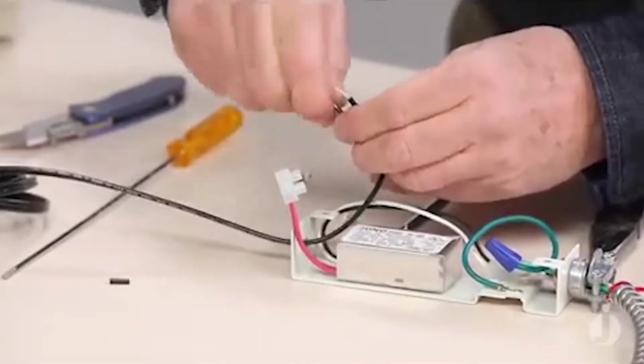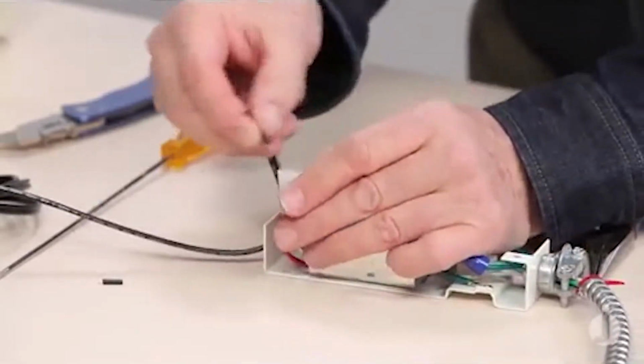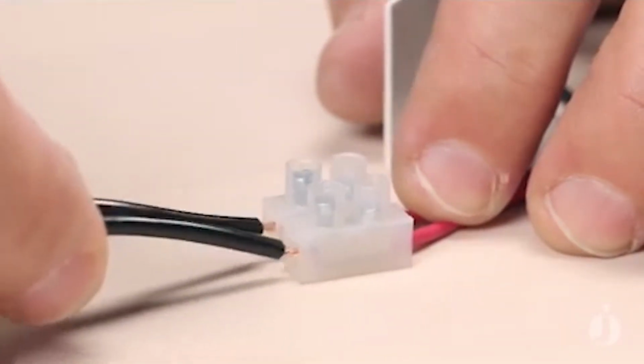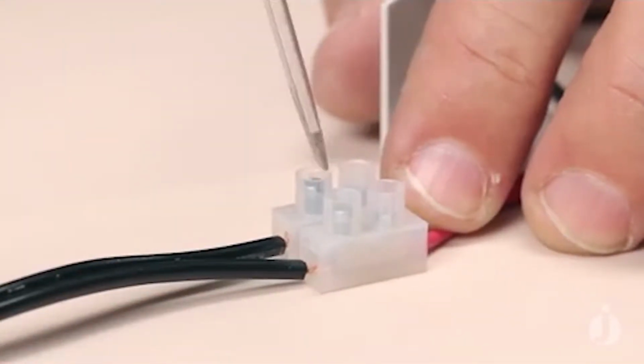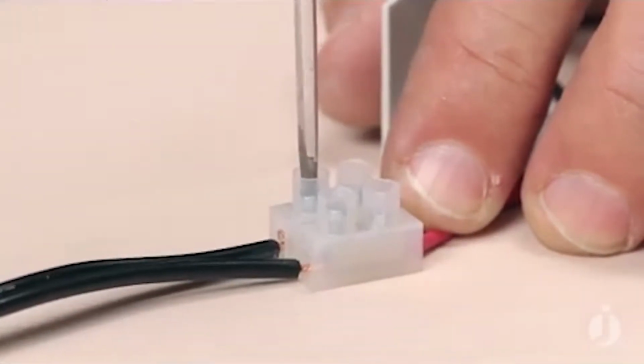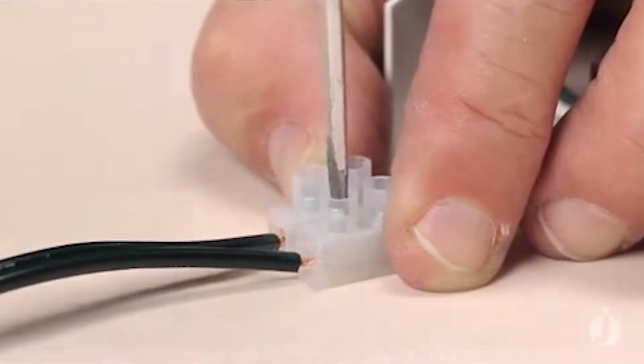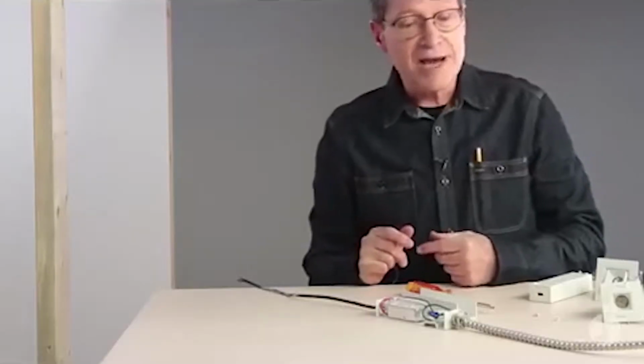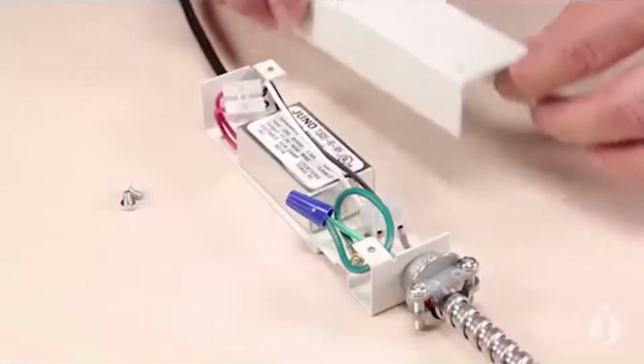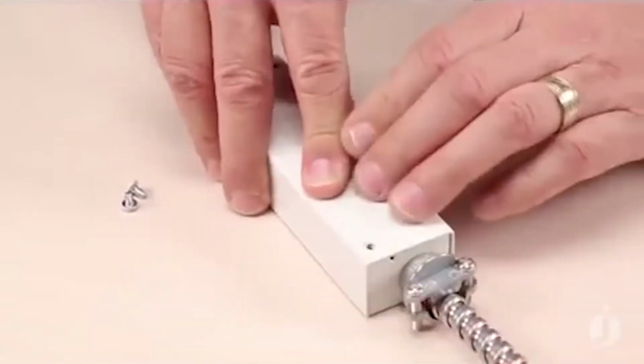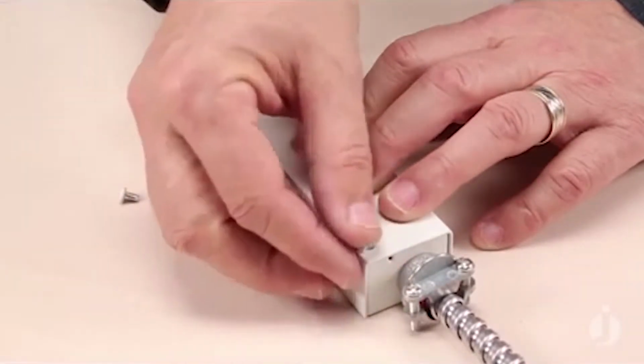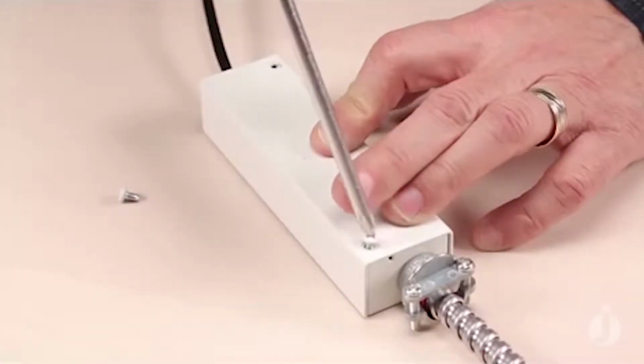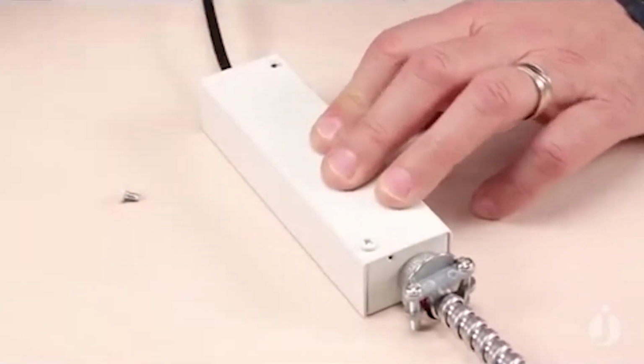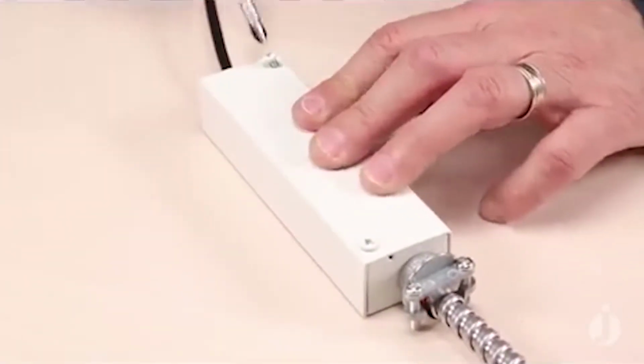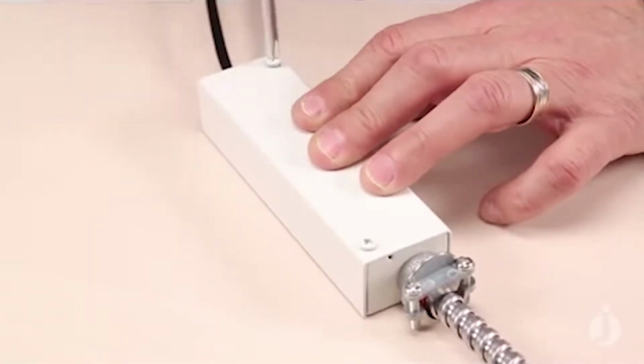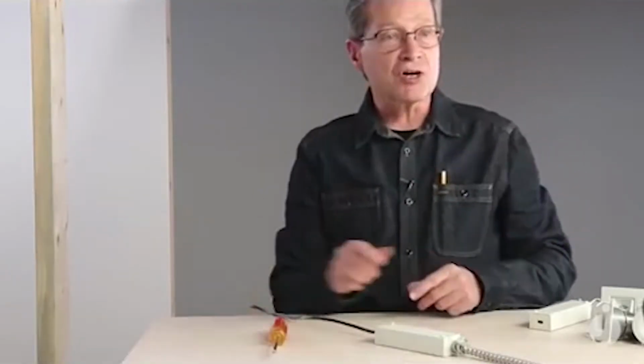You may notice here there's no black wire and white wire. We just have two red wires going into two black wires. With low voltage systems, we are not required to observe any kind of polarity. I'm tightening the screw now down onto my first wire and my second wire coming next. Now that we've attached our primary and secondary leads to the transformer, we're ready to fasten the cover back on. So I'll just place that over the pre-drilled holes in the chassis and insert those little Phillips screws. And we're ready to connect our fixtures.